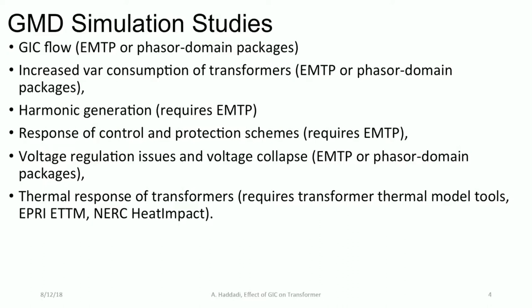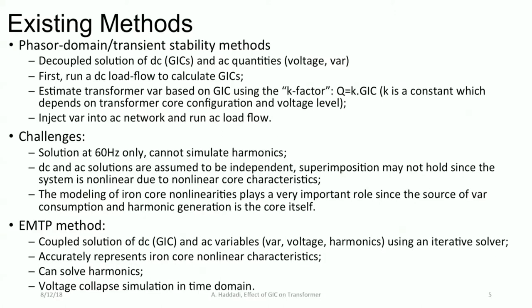The simulation studies required by the NERC standard include: GIC flow — calculating the DC currents circulating in transformers and transmission lines — transformer VAR consumption, harmonics, the response of control and protection systems, voltage regulation and voltage collapse issues, and also thermal response of transformers. Existing methods can be broadly categorized into phasor domain and EMT-type methods.